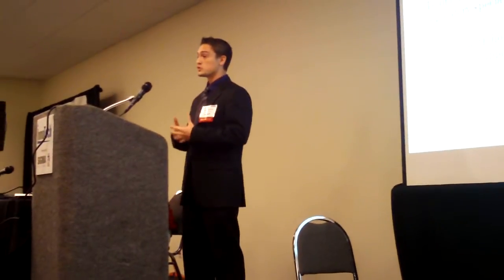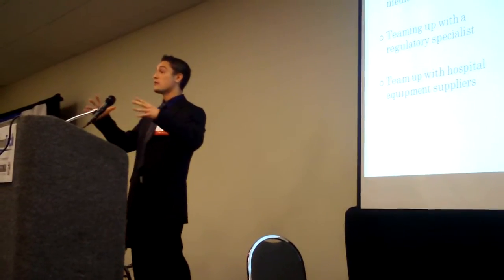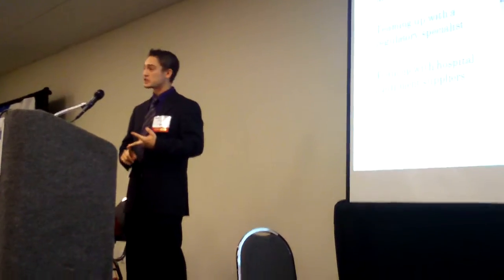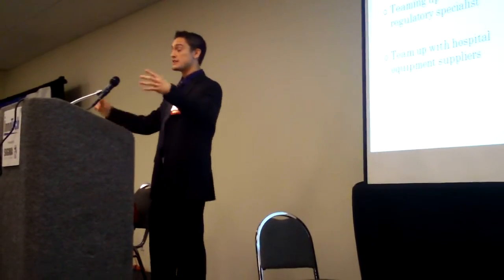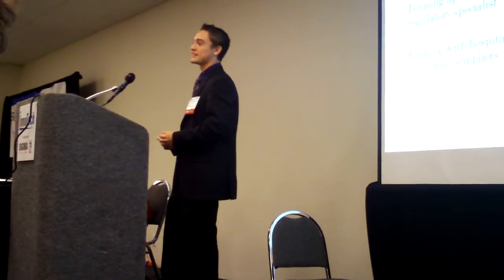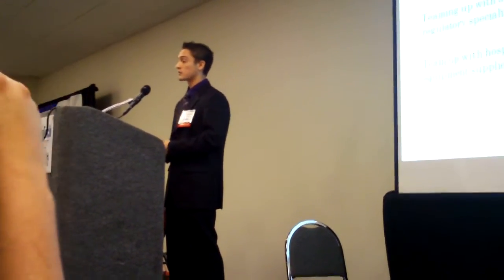In the near future, we're going to be teaming up with a medical manufacturer to do our first test runs to prepare our FDA filing, and also teaming up with regulatory specialists. I myself used to work for KCI in the R&D department, specifically in verification and validation, where I tested their future products to FDA standards. I designed test protocols and test procedures, and the information gathered was compiled into the 510K by another team member. So we recognize our limits, and that's one of the reasons we need to bring more people on. After that step, we'll be teaming up with hospital equipment suppliers to get our product on the market.